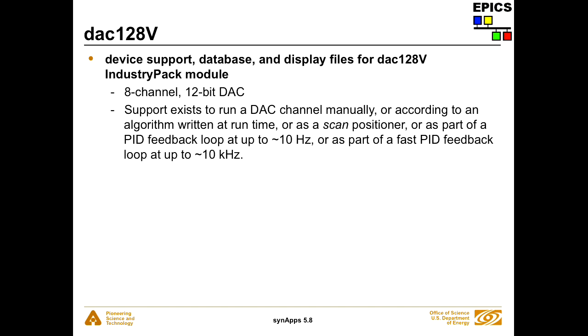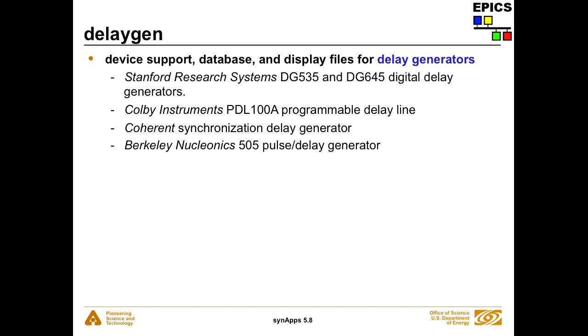The DAC128V module is for a specific industry pack D-to-A converter. You can run it manually for a single D-to-A conversion, run it to an algorithm — generate a sine wave, for example — use it as a scan positioner, use it as part of a slow feedback loop at up to 10 Hz involving EPICS record processing, or use a fast PID feedback loop done entirely in an interrupt service routine at up to around 10 kHz. The delay generator module supports several different delay generators. I don't know very much about this module — that's Don Arms's area.